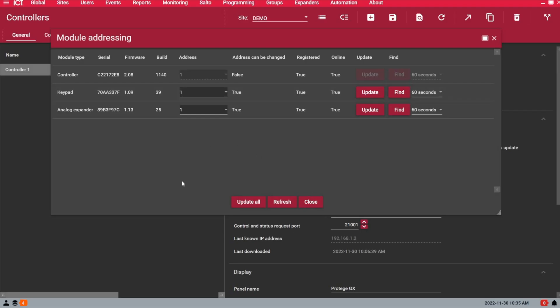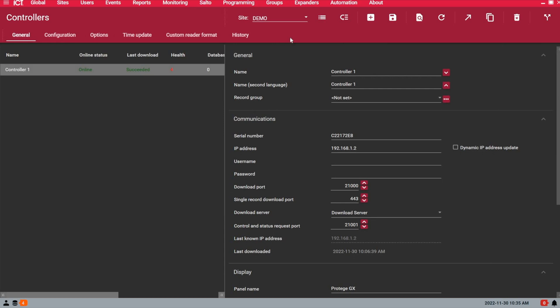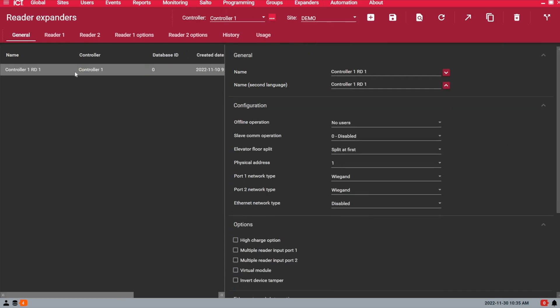So the first step is to make sure that under expanders and reader expanders, you have at least one reader expander created. In this example, I want to use reader expander address 1 as the onboard reader port or onboard reader expander for my main controller. Obviously then if you have more reader expanders on the RS-485 network, the next available address will be address 2, 3, and so on.